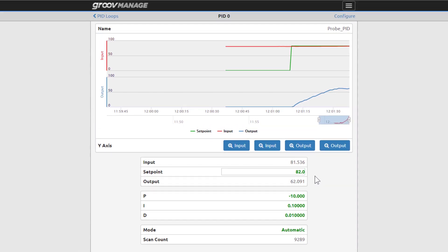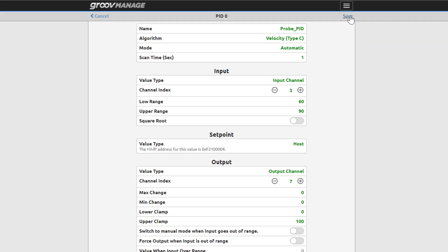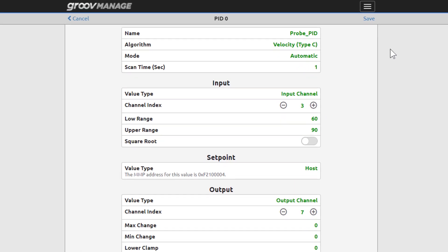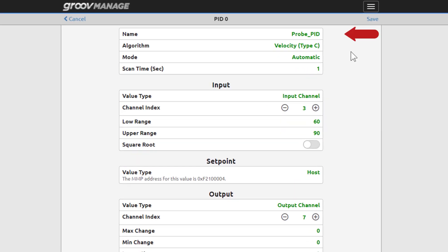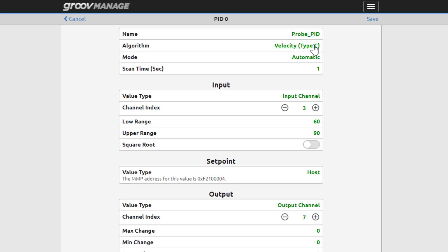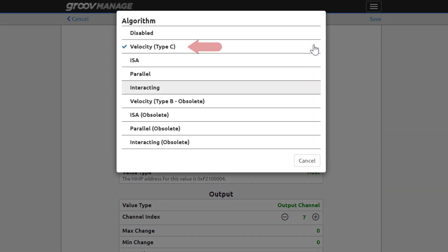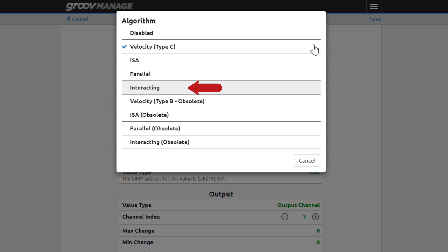Click configure to see how a PID is set up. You can name the PID, and you have a choice for the algorithm. The mathematical formula used to calculate the PID. The default algorithm is velocity type C, but if you're more familiar with the ISA, parallel, or interacting algorithm, choose it for your PID controller. No one formula is right or wrong for a particular process.